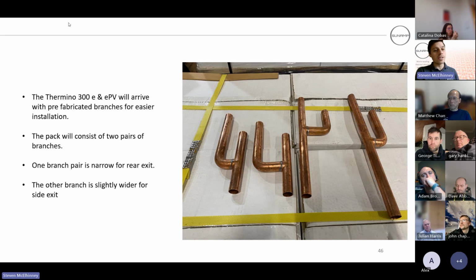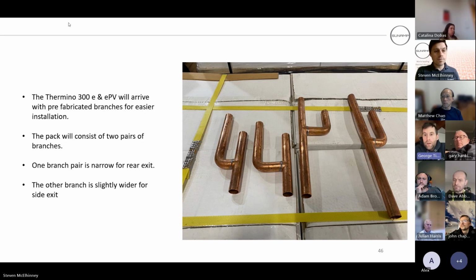I mean, that was a 70 though, but if you're going up to a 300, you're hoping that you've got the capacity there to deal with it. One thing you would have to bear in mind is you wouldn't have the flow rates as well, so you'd have to reduce that flow rate running through the heat exchanger. The twin ports, there's presumably two heat exchangers inside the battery. Are they sat in the same place, if you see what I mean? So they're not taken from the cold bit and the hot bit. They're taken from the whole capacity of the battery, each heat exchanger.